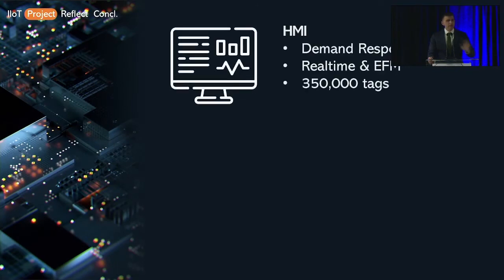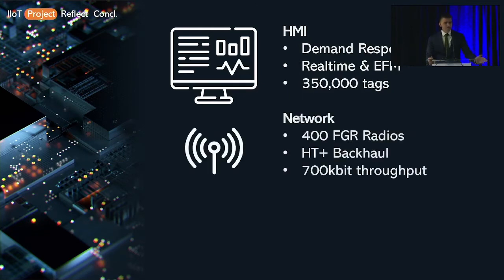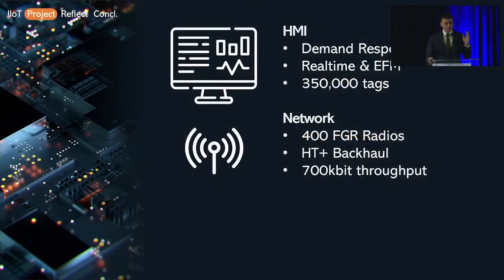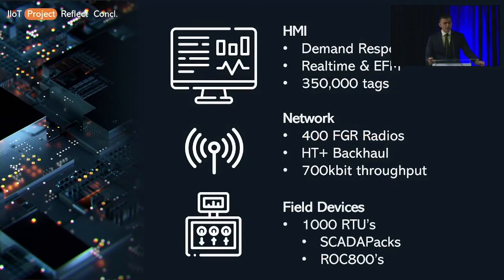So what were we working with? Well, they had a traditional HMI that was doing the demand and response for their polling built into it. It was doing real-time and EFM collection, and it was bringing back about 350,000 tags across 400 FGR radios that, on a good day when the sun was shining and there were no pine trees growing, got 700 kilobits a second through. And it was talking to about 1,000 RTUs and PLCs, roughly evenly split between SCADA packs and ROC 800s.